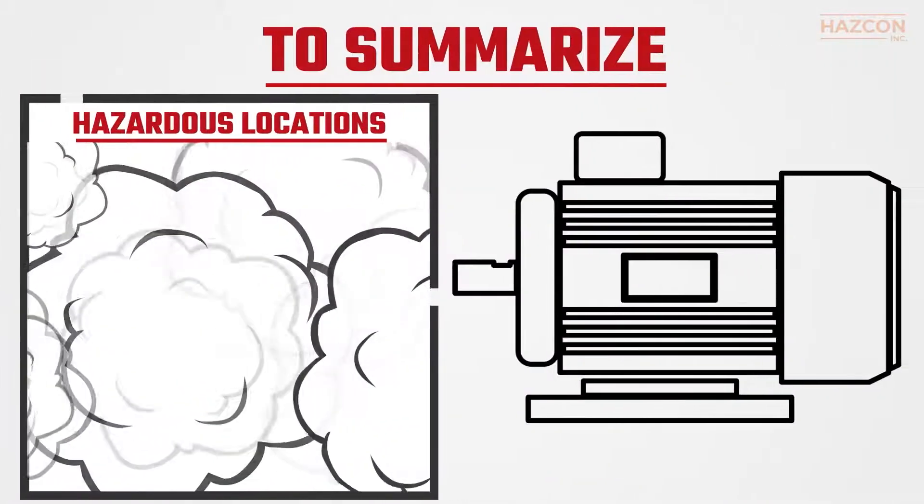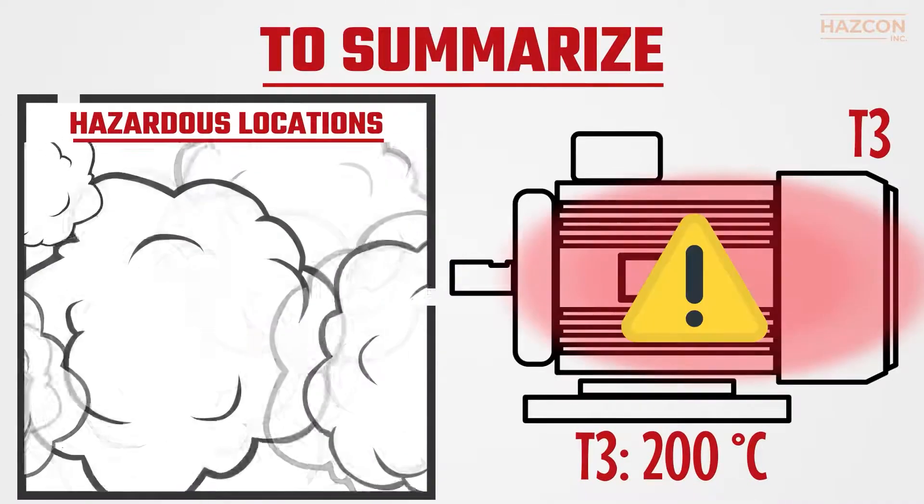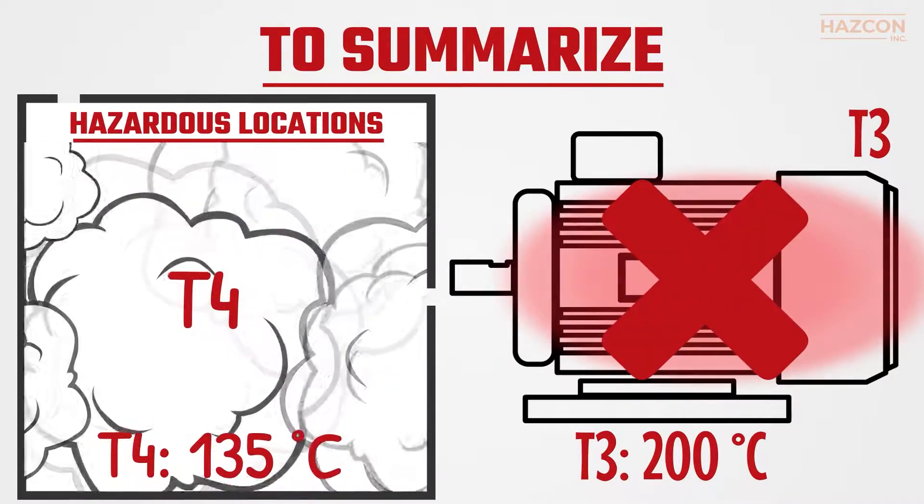But if a hazardous location application requires a T4 rated device, a T3 rated product will not be suitable.